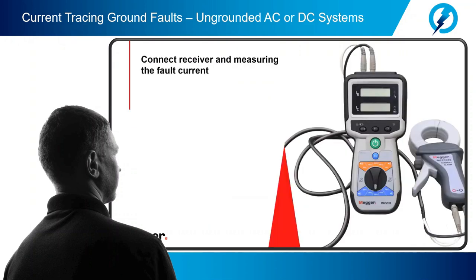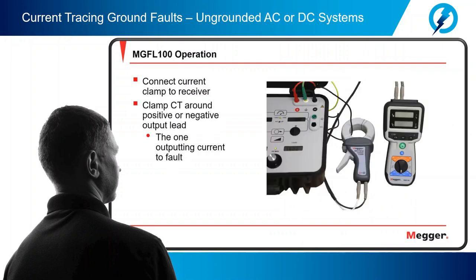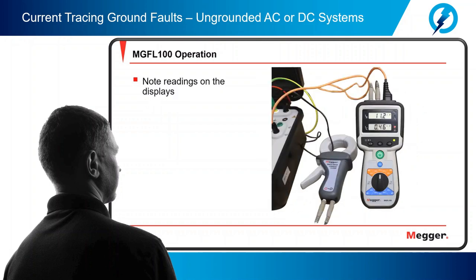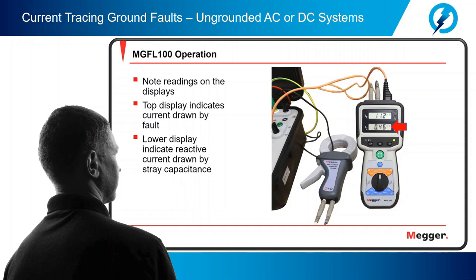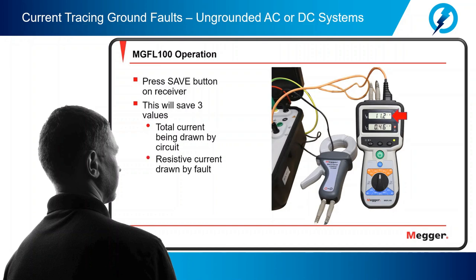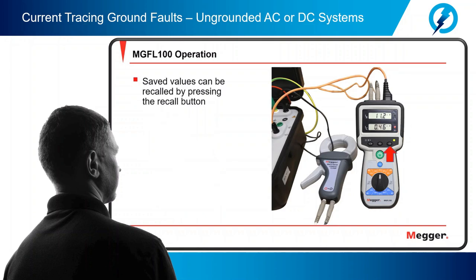Now we are ready to evaluate the fault. Connect the current clamp to the receiver and place the current clamp around either the positive or negative output lead — whichever is outputting current to the fault. Connect the sync cable between the receiver and the transmitter. The top display will indicate the current the fault is drawing; the lower display will indicate the reactive current drawn by stray capacitance on the circuit. It is the actual fault current on the top display that will be traced. Press the save button on the receiver to save three values: the total current being drawn by the circuit, the resistive current being drawn by the fault, and the reactive or leakage current drawn by stray capacitance. These values can be recalled at any time by pressing the recall button.